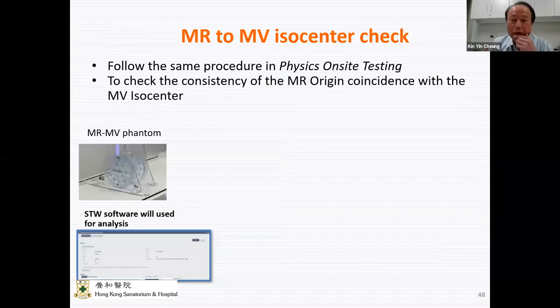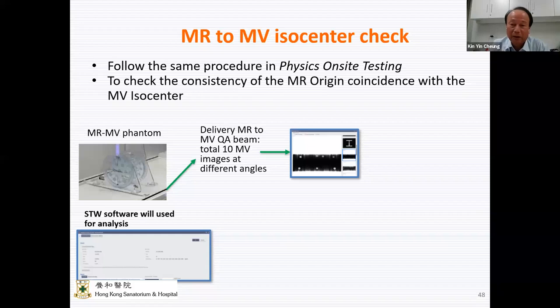And we also do a monthly MR and MV isocenter alignment check. So we use a phantom supplied by Elekta, and we run an automatic sequence using the MR control to run the sequence. It first uses the MV imager to take images of the phantom at several different angles, and then calculates the isocenter location.